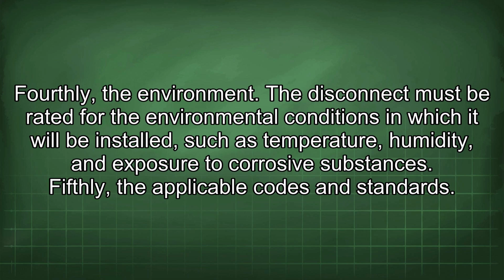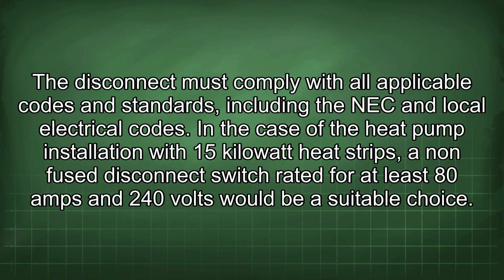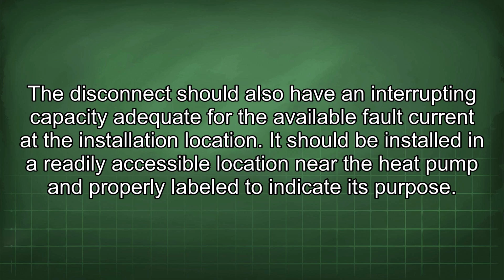Fifthly, the applicable codes and standards. The disconnect must comply with all applicable codes and standards, including the NEC and local electrical codes. In the case of the heat pump installation with 15 kilowatt heat strips, a non-fused disconnect switch rated for at least 80 amps and 240 volts would be a suitable choice. The disconnect should also have an interrupting capacity adequate for the available fault current at the installation location. It should be installed in a readily accessible location near the heat pump and properly labeled to indicate its purpose.